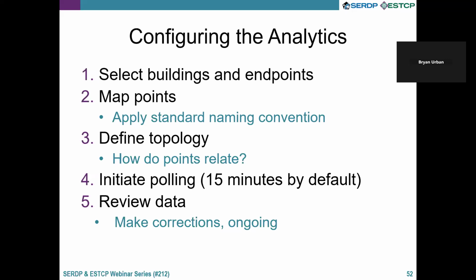Once the points are mapped and the topology is defined, you can initiate polling. They have a database and start storing data for all the endpoints on the network every 15 minutes, and you can fine-tune that—if certain points need micro trends or faster polling, you can adjust those frequencies. Then they do a data review and make corrections on an ongoing basis. Again, most of this work is done by the analytics vendor, not the facilities team.